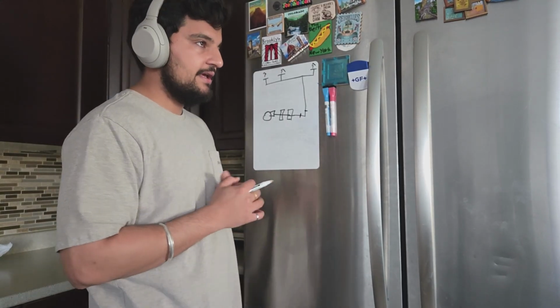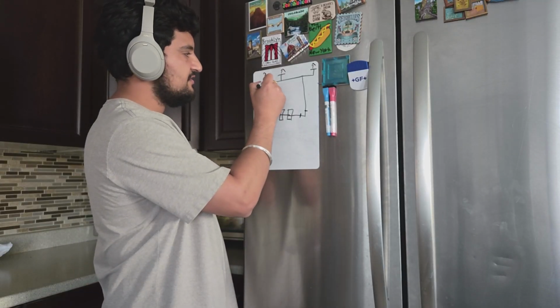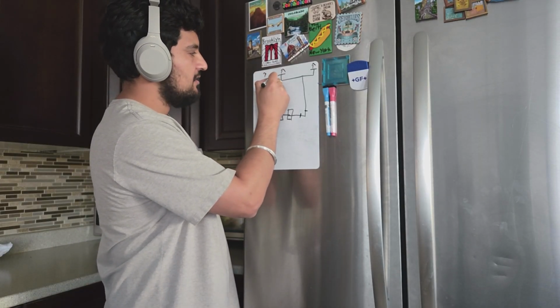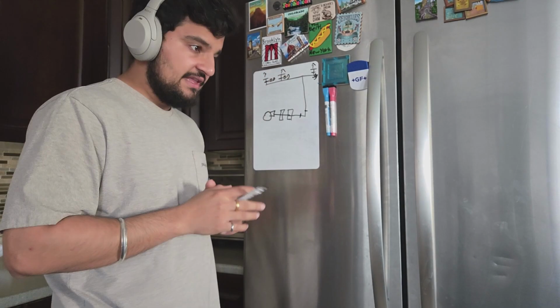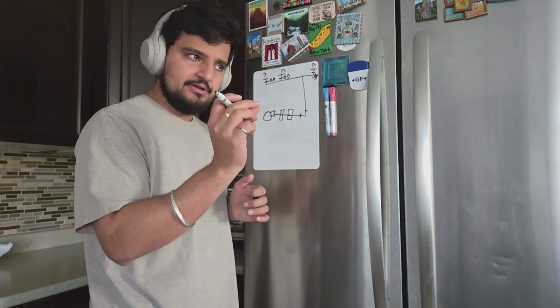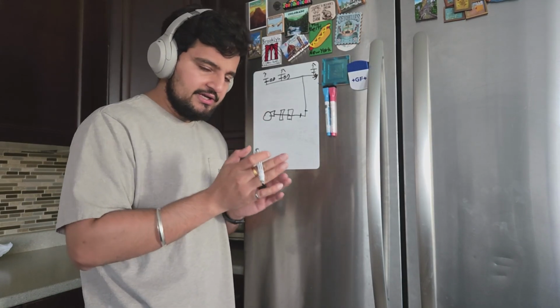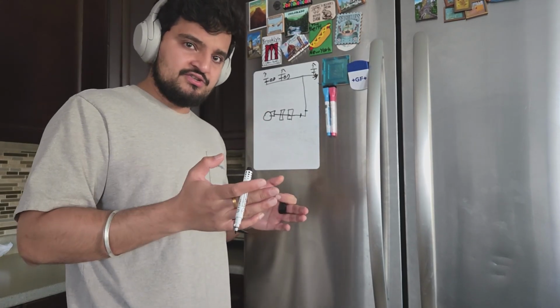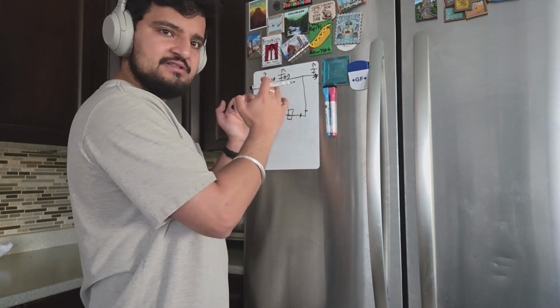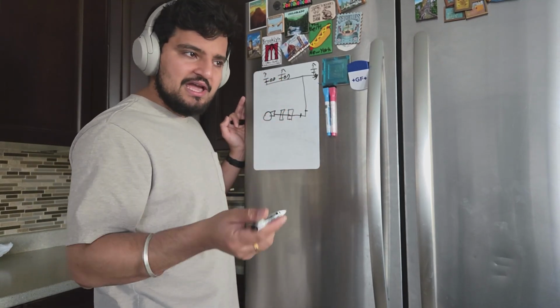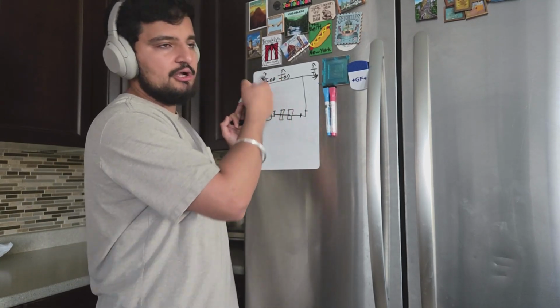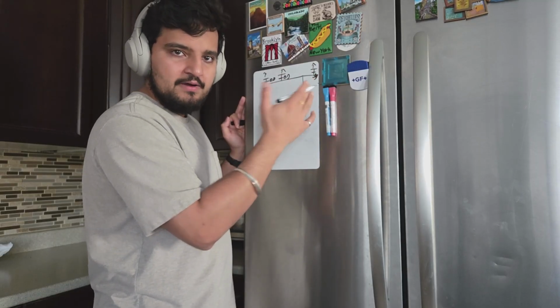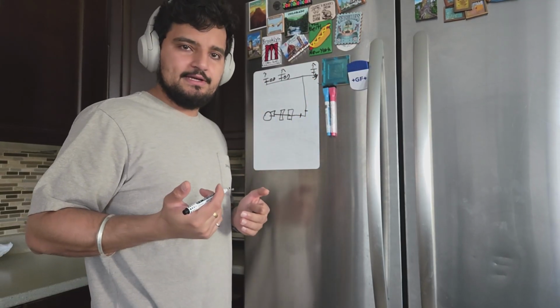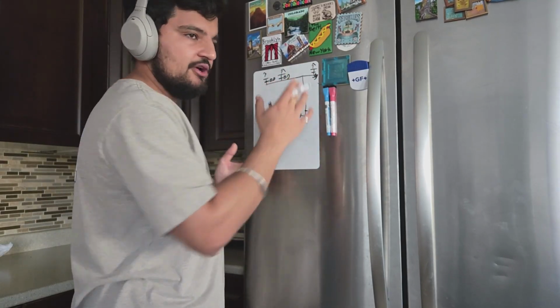One more thing is all your registers in the floor have something called a balancing damper. Now, a balancing damper is basically like a little thing that you can adjust to increase or decrease the pressure through that floor register, which increases and decreases the flow into that room, right? So you have a room that faces the sun, you want more air to go into that room versus a room that's facing away from the sunlight. So these dampers kind of help you balance that.